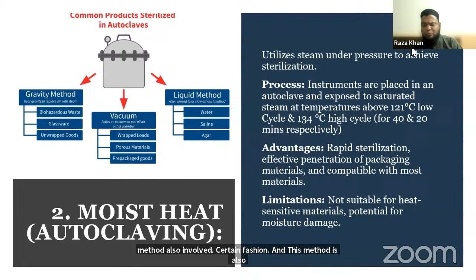Let us discuss the autoclave process in a little more detail. What is an autoclave? An autoclave is a closed chamber in which objects are steamed and heated with high pressure and high temperature, usually above 100 degrees centigrade, like 121 and 134 degrees centigrade. We usually use three cycles or three types of autoclave: the gravity method, the vacuum method, and the third one, the liquid mode. Usually in a modern autoclave, all three cycles are included in a single autoclave.